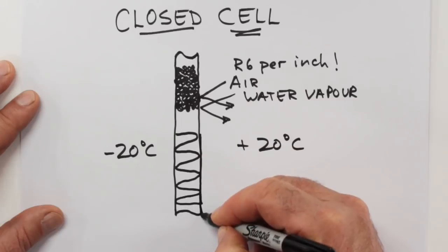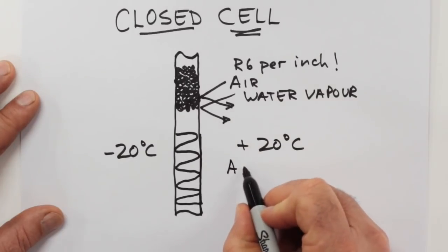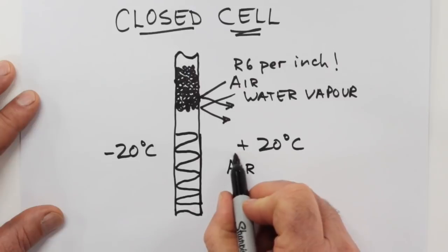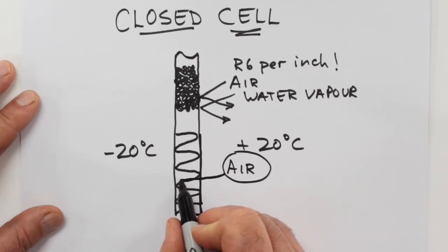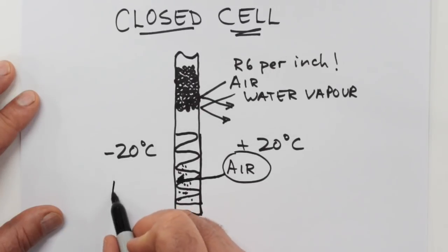Let's imagine for a moment that there is no vapor barrier on the inside as there normally is on a wall of this kind. If indoor air is allowed to pass into the wall because of the absence of the polyethylene vapor barrier, it's going to cool and eventually it's going to condense and drops of liquid water will appear within the wall. This of course is going to lead to mold and rot.